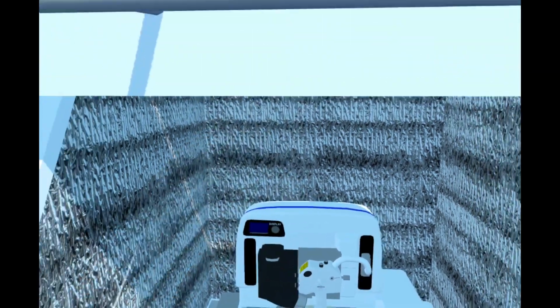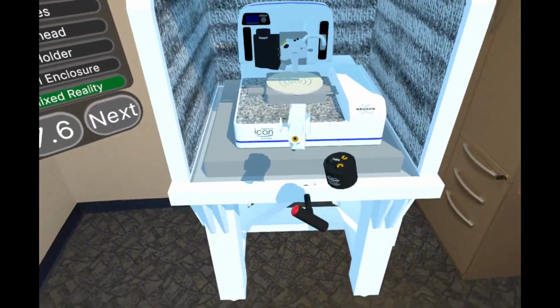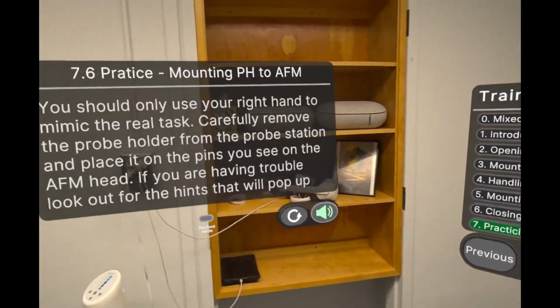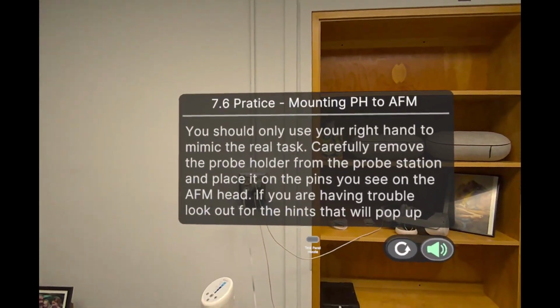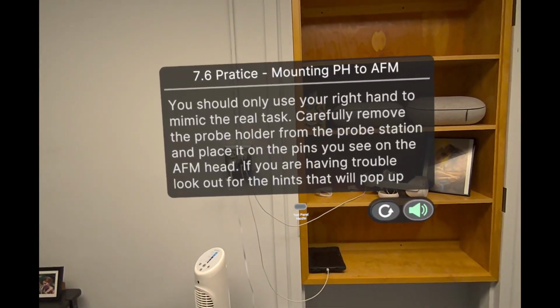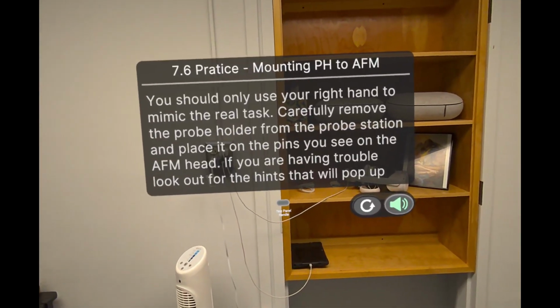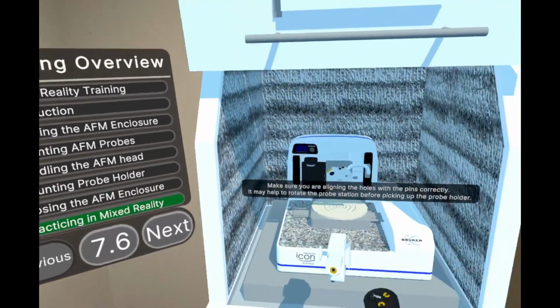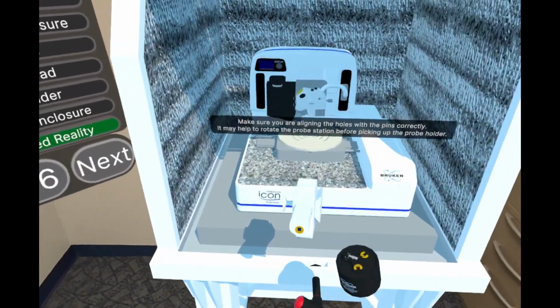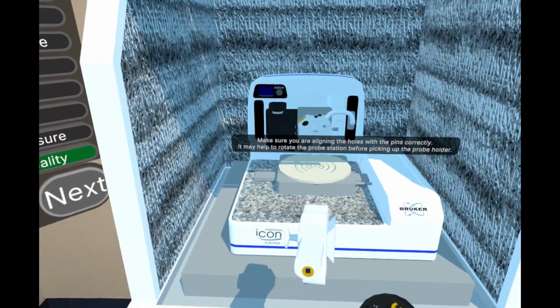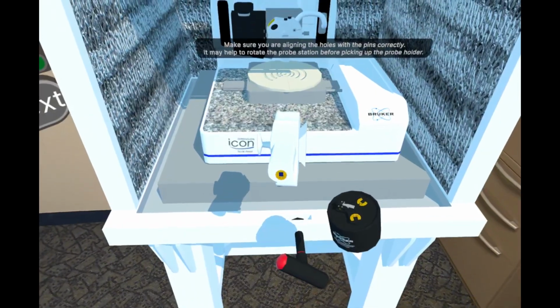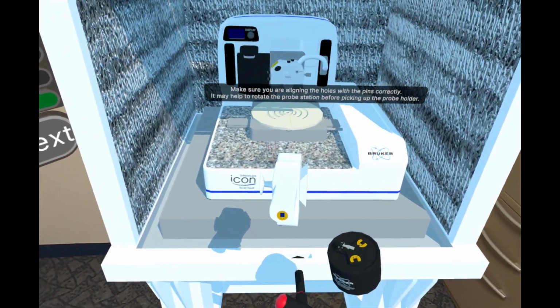Now that the probe has been loaded into the probe holder and you've lifted the AFM head out, the probe holder can be mounted to the AFM head. For this task, you should only use your right hand to mimic the real task. Carefully remove the probe holder from the probe station and place it on the pins you see on the AFM head.